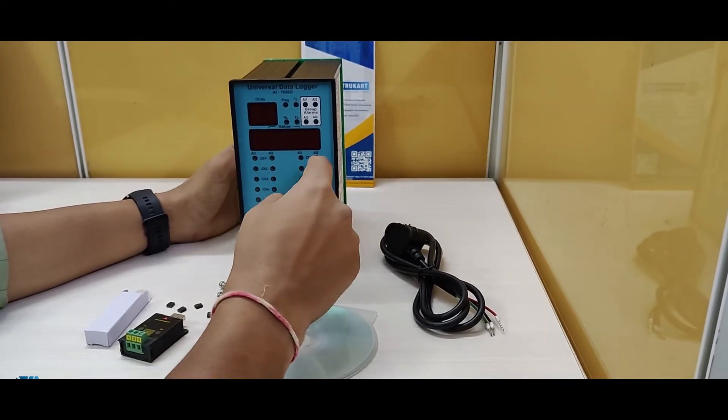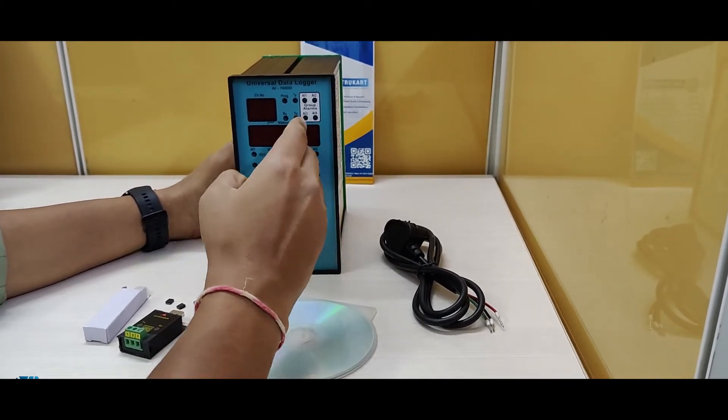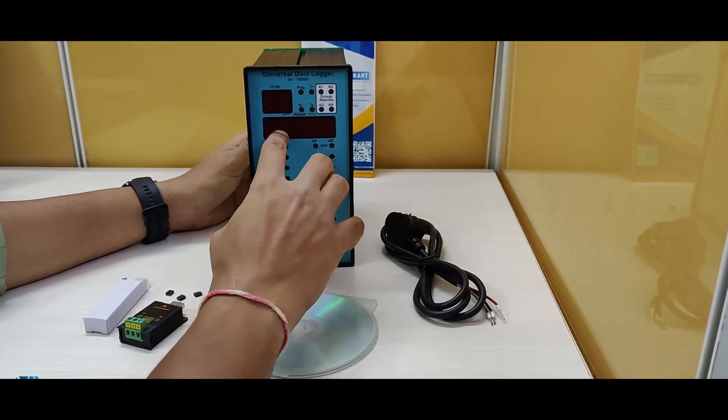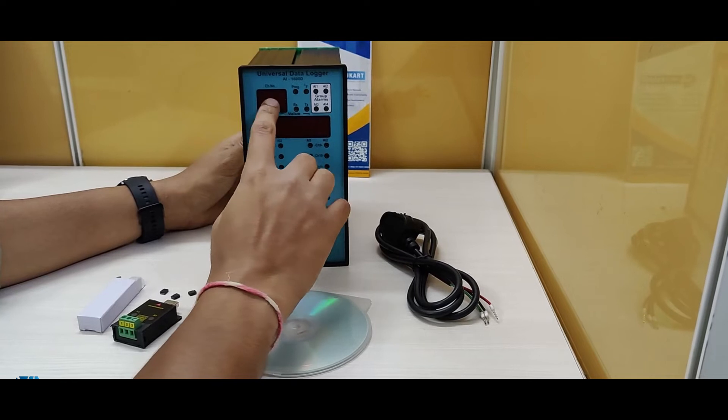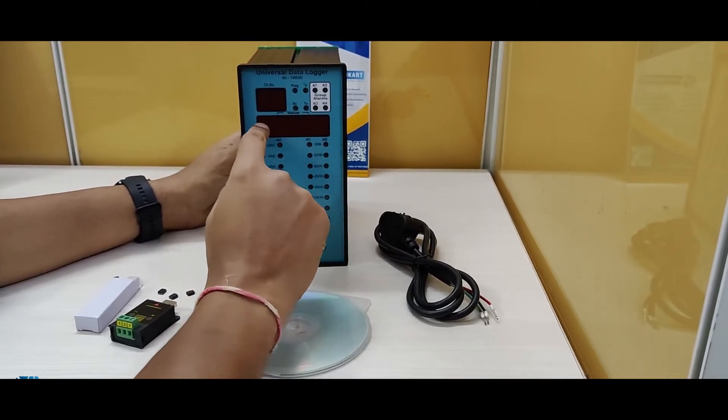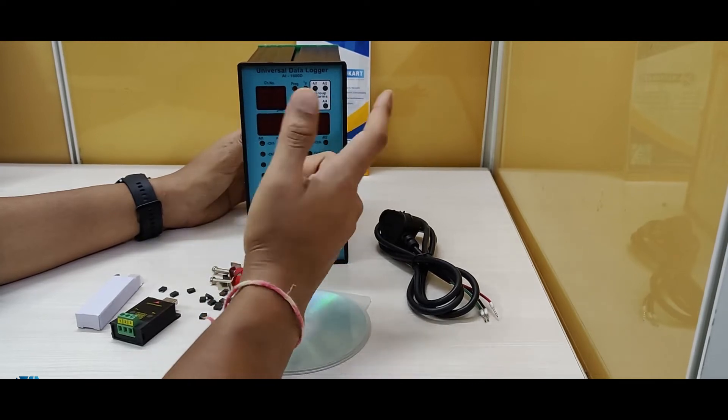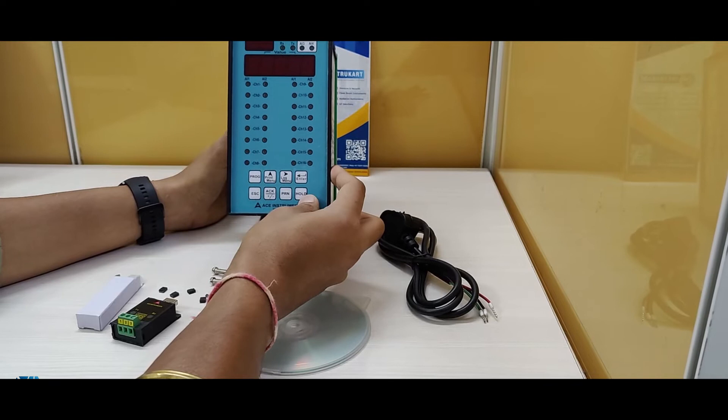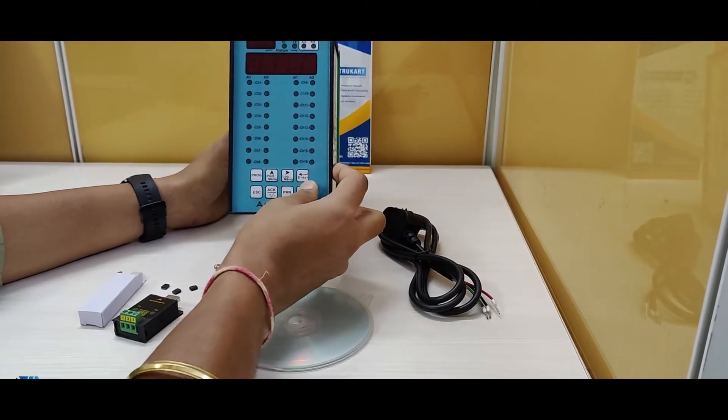Now this can show all the 16 channels simultaneously in this particular device. As you can see, there is one screen which is showing the channel number starting from 1 to 16 and the process value from 1 to 16 on a toggle mode. You have the front 8 keys to navigate.